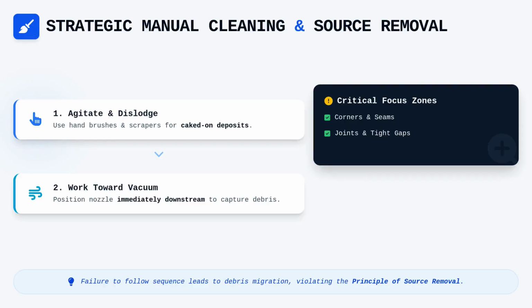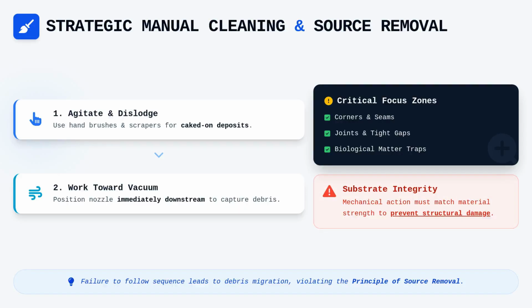Corners, seams, and joints are particularly problematic because they act as traps for fine dust and biological matter that the airflow frequently misses. By using curved corner brushes or crevice tools that reach into these tight gaps, you ensure that the entire internal surface area complies with the expectations for a clean duct system. Always remember that the mechanical action must correspond to the material's structural integrity to avoid damage to the substrate itself.